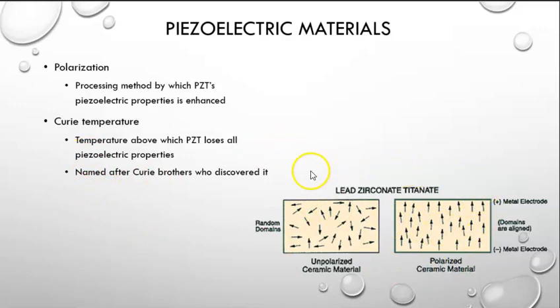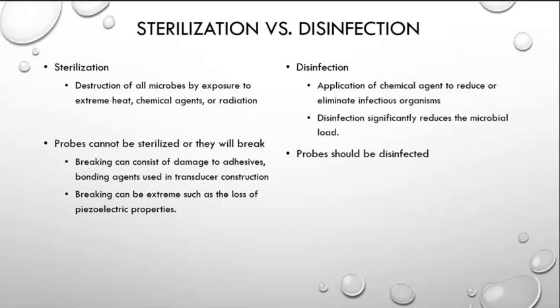If you take a chunk of PZT material and you heat it up to a particular temperature called the Curie temperature, it will lose all of its piezoelectric properties. So you take a nice chunk of crystal, heat it up to a certain temperature, and all of a sudden it has no piezoelectric properties. So that is one reason, not the best reason, but one reason why we don't put our probes in autoclaves, is we don't want them to accidentally get overheated and lose their ability to detect sound. So we avoid autoclaves, and we avoid sterilizing our probes because that would ruin them.